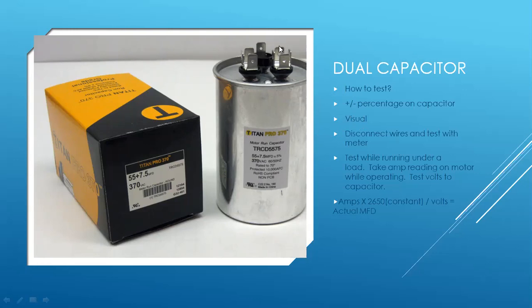Also do a visual inspection. If you've got wires on here that are all bubbled up, chances are you have a loose connection there. And if you have what looks like a pop can or an exploded pop can where it's all bubbled up here in the top, then you know it's bad. It's shorted.